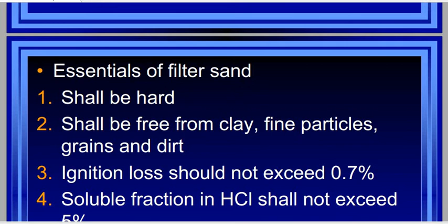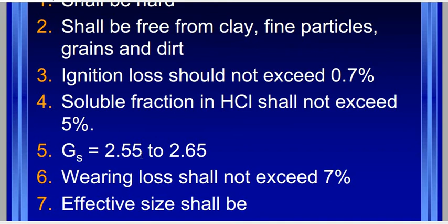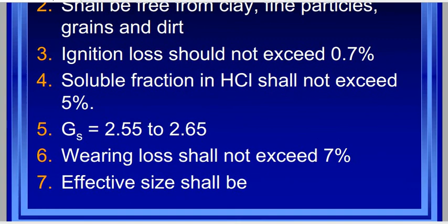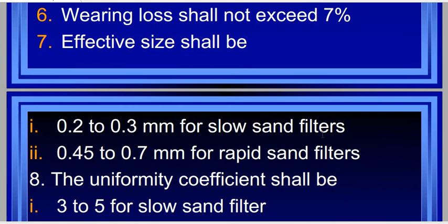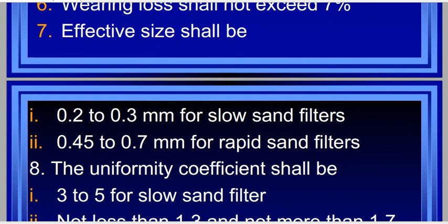Now what are the essentials of filter sand? It should be hard, free from clay and other fine particles. Ignition loss should not exceed 0.7%. Soluble fraction in HCl should not exceed 5%. Specific gravity should be 2.55 to 2.65, wearing loss should not exceed 7%, and effective size shall be 0.2 to 0.3 mm for slow sand filter and 0.45 to 0.7 mm for rapid sand filter. So these are the essential requirements for the sand.